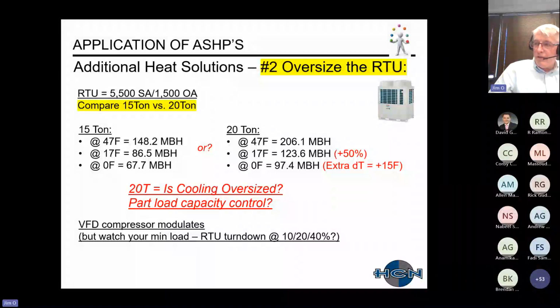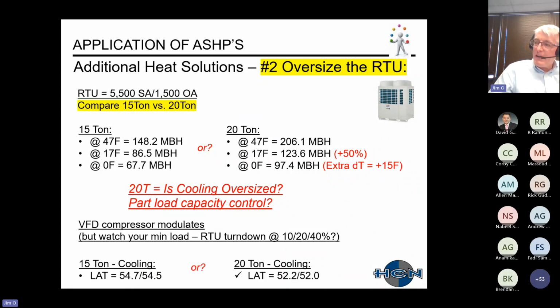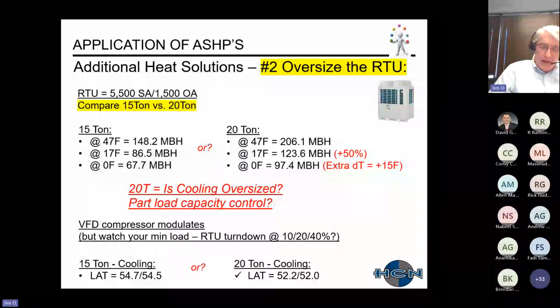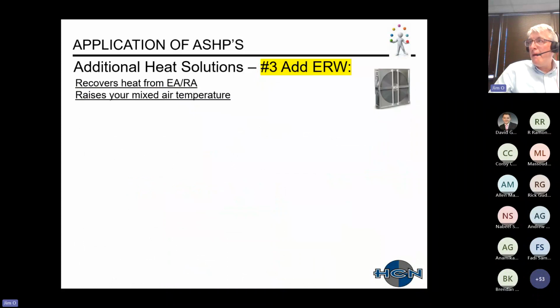Just always be careful with VFD compressors. The typical VFD compressor has a turn down of 30 to 40%. So it depends on how many compressors you have in your unit, et cetera. So just, once again, be careful of your turn down. For this example here, you had a 15-ton with the leaving air temperature of that, and you had a 20-ton with the leaving air temperature of a little bit lower. Once again, in my opinion, it was 2 degrees. You weren't really oversizing the unit anything drastically or anything that could really get you into trouble.